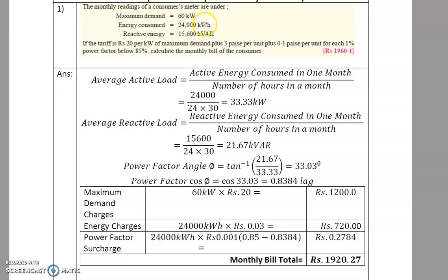The maximum demand is 60 kW, energy consumed is 24,000 kWh, and reactive energy is 15600 kVAr. The tariff is rupees 20 per kW of maximum demand, plus 3 paise per unit, and 0.1 paise per unit for each one percent power factor below 85%. This is a power factor type tariff.